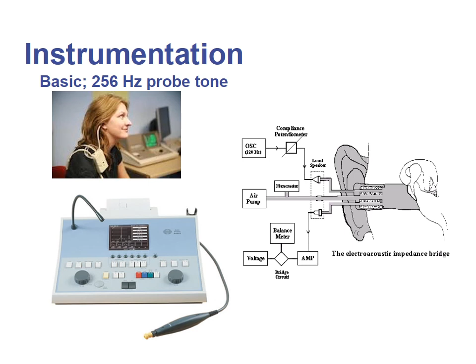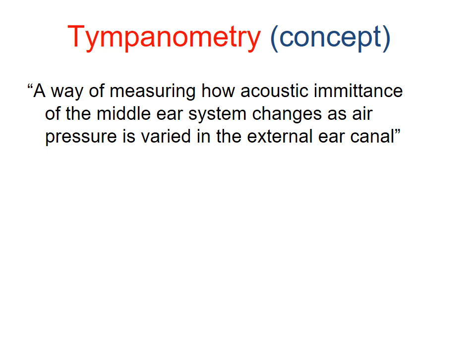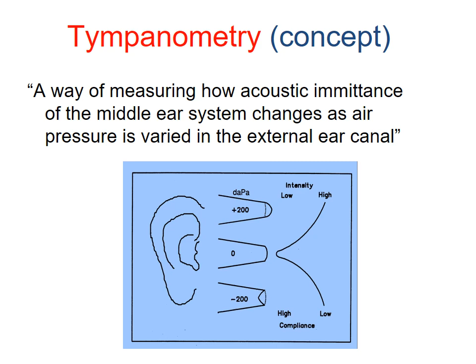And the concept in tympanometry is to measure how the acoustic impedance of the middle ear system changes as air pressure is varied in the external ear canal. Whenever the pressure in the external ear is equal to the pressure in the middle ear, there will be a maximum compliance. But whenever there is a change, whether positive or negative, there will be more reflection of sound and a minimum compliance or transmission of the sound.